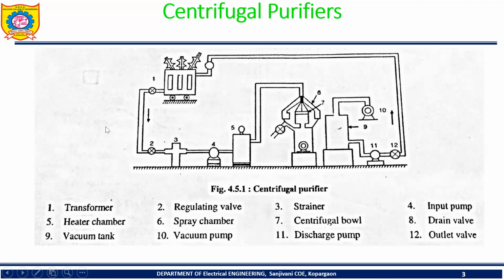So the heated transformer oil in the heating chamber is shifted through this pipe to the spray chamber. Now the small spray is sprayed over the centrifugal bowl. This is a rectangular type of bowl we are seeing. This is the centrifugal rotating bowl, which rotates at about 8,000 rpm. Because of this high speed rotation and the spraying of the oil, centrifugal action takes place, and because of centrifugal action, the heavy particles are separated into this separate output chamber.